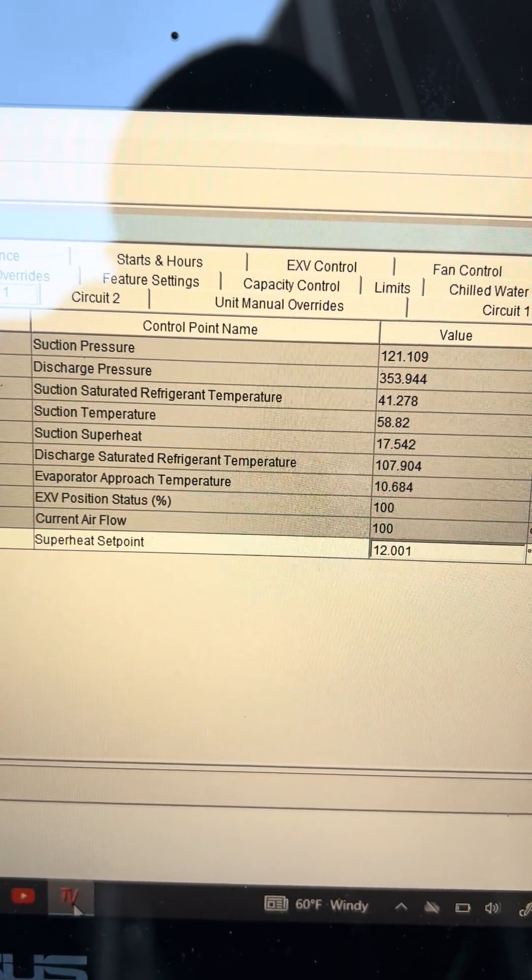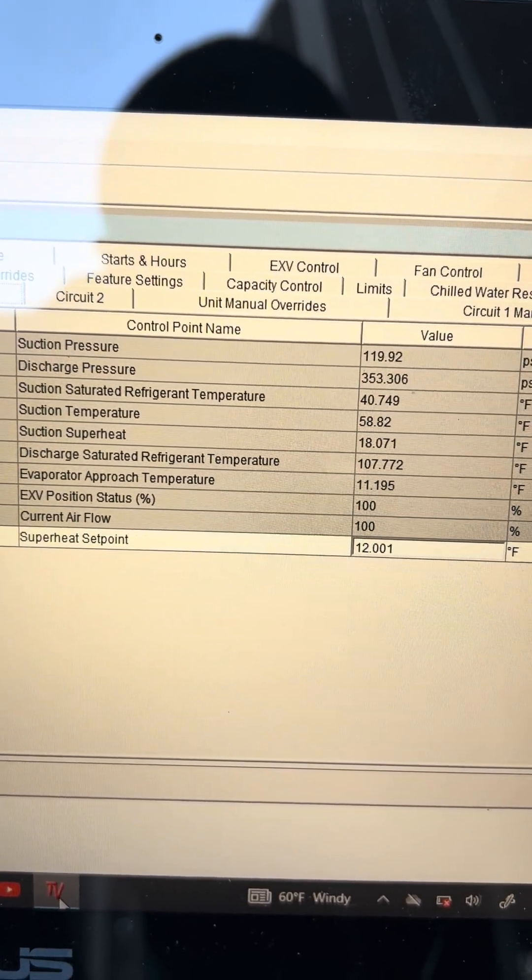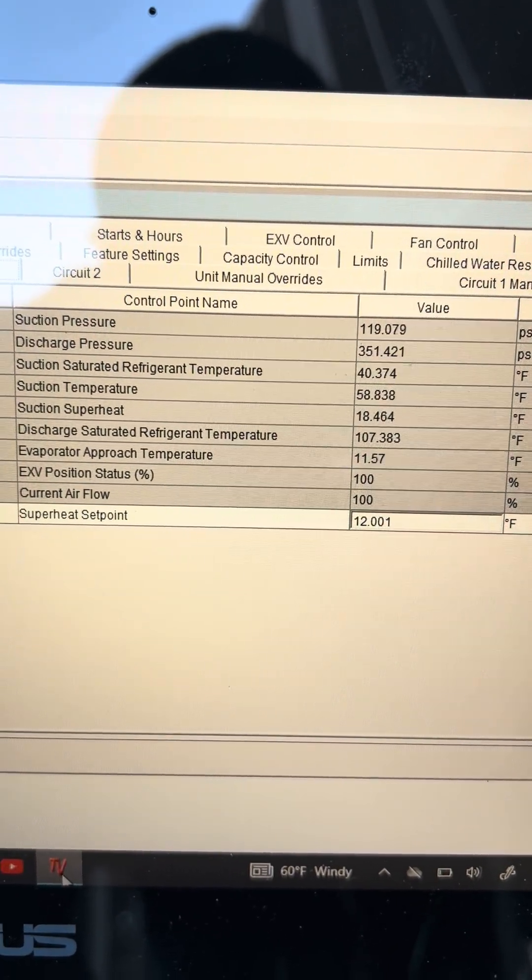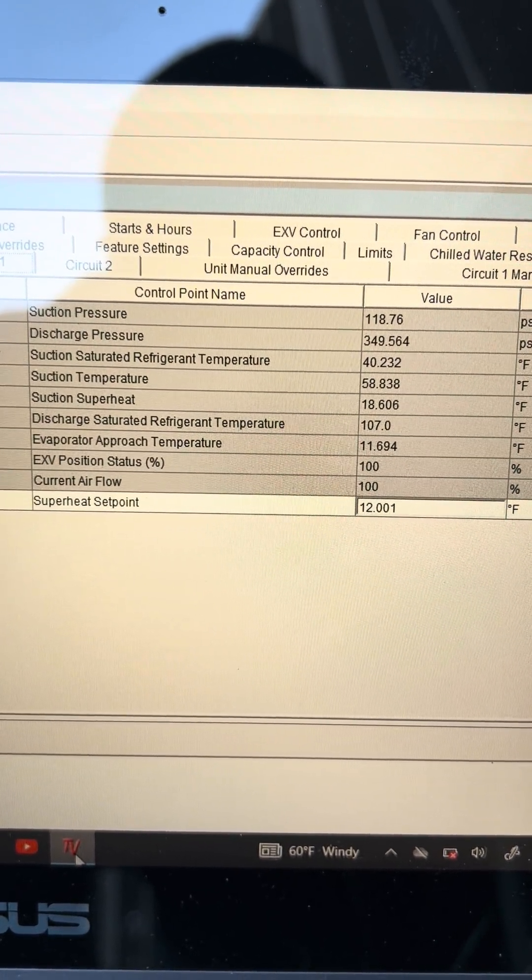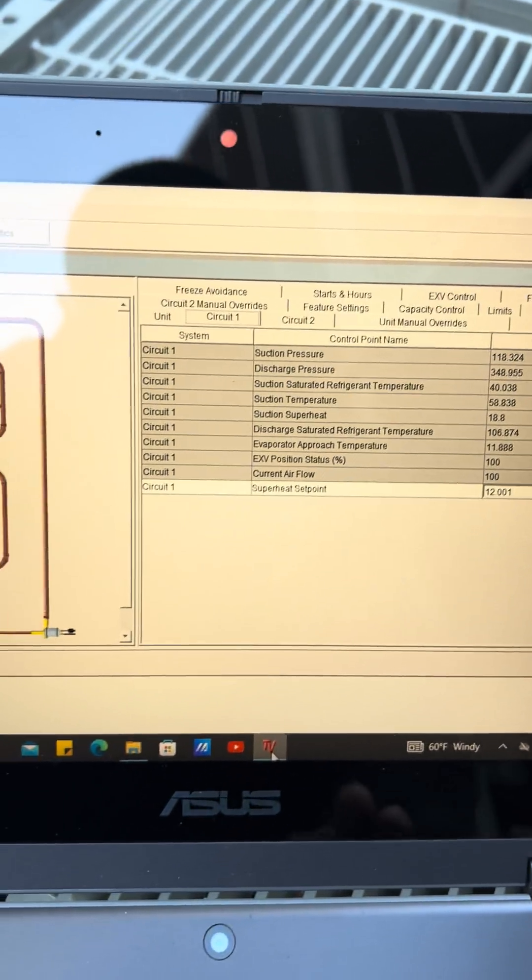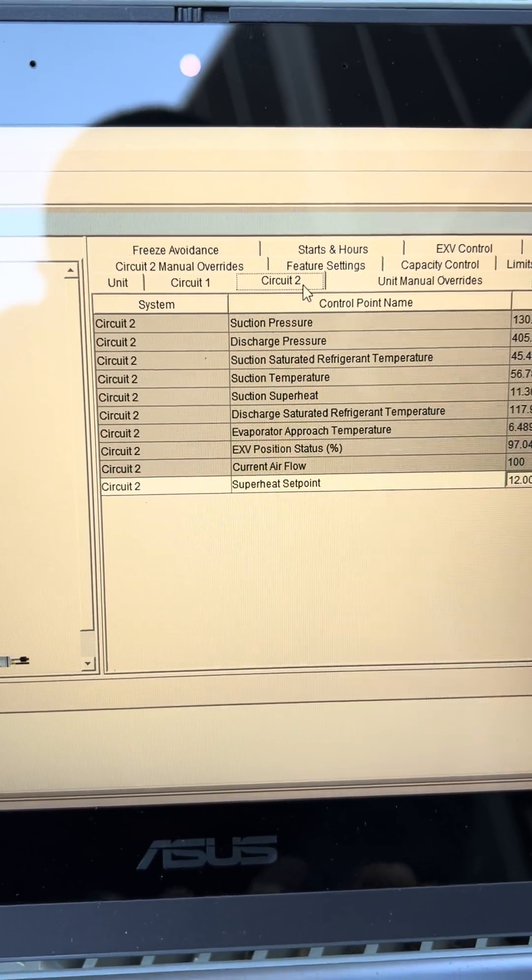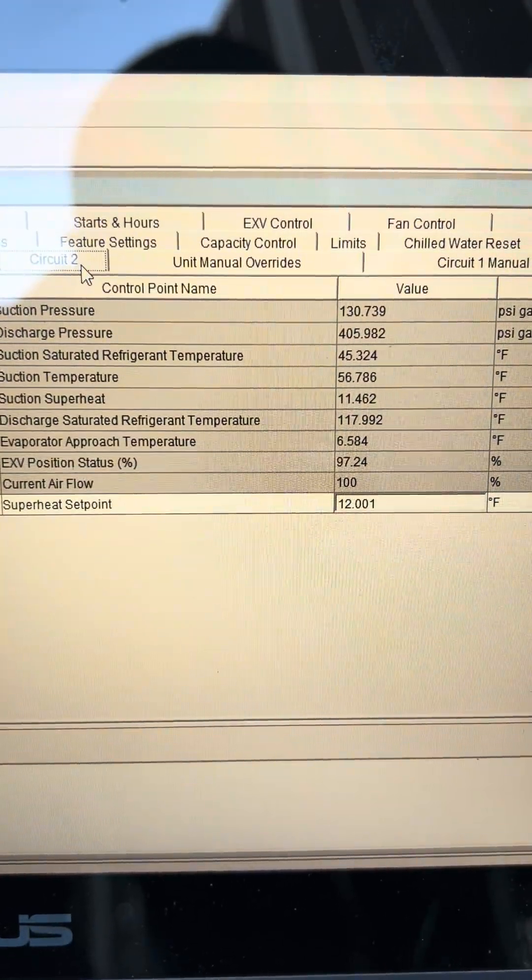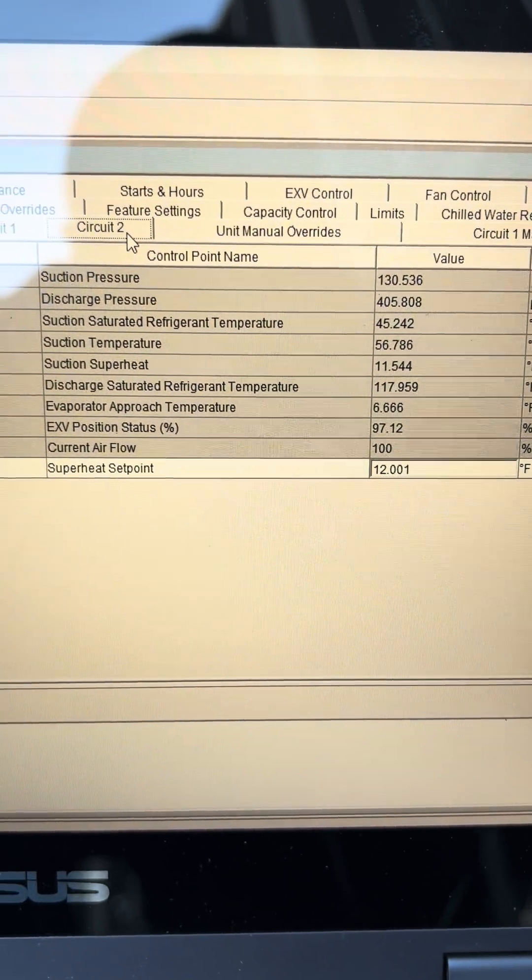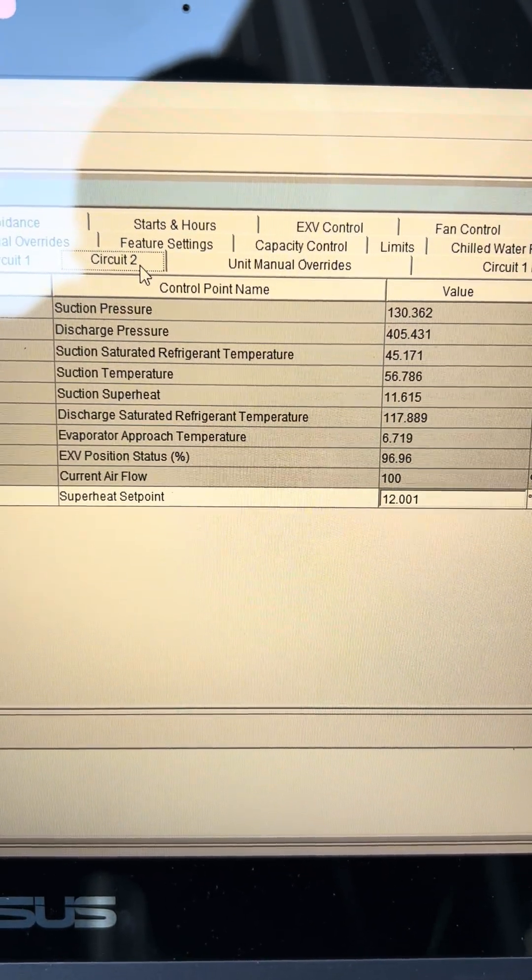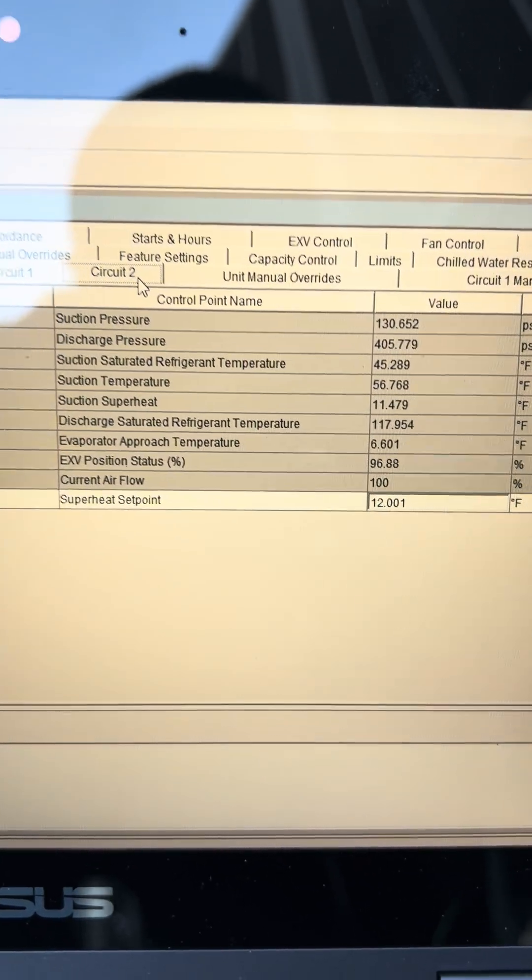That's circuit number one, so suction pressure is definitely coming up. Let's see circuit number two in comparison before my computer dies. Circuit number two we got 130 and 405, 56 suction pipe and superheat is at 11. Approach 6.4 and my EXV is at 96 percent.